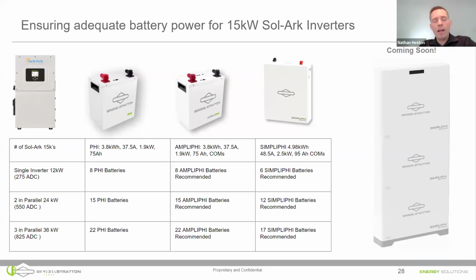So if there's grid down and there's solar available, it can use the solar to power some of those loads. You can saturate the DC bus with 15 kilowatts of solar coming in, or 19 kilowatts of solar coming in, and 15 kilowatts of that can be used to power loads and charge batteries. If solar is not available, you exceed the power output of the inverter from batteries, and grid is not available, then if you have a generator connected, it will start up the generator. If you don't have a generator connected, you can get into an overpower situation and the inverter can restart with a fault. So that's why I'm saying if you need the full power output of the inverter, you should size your battery bank appropriately.